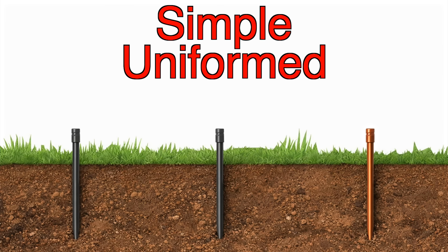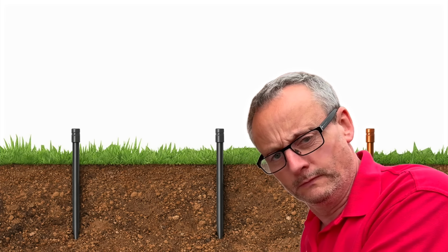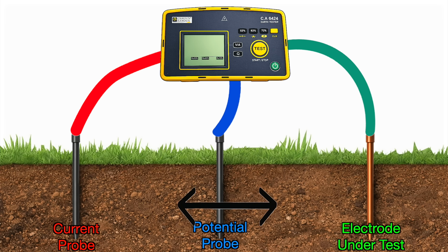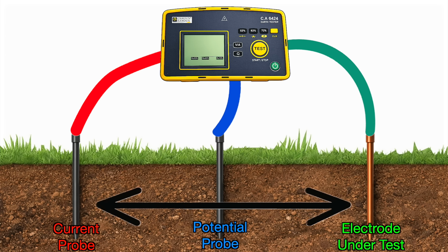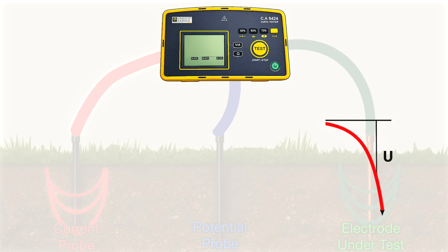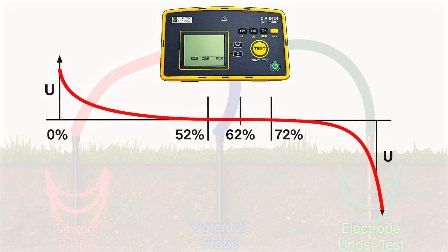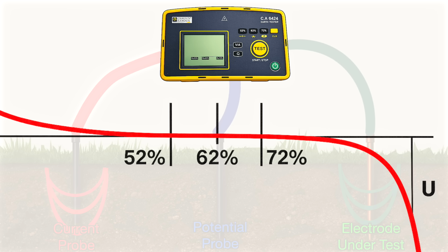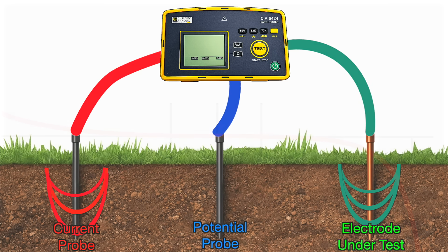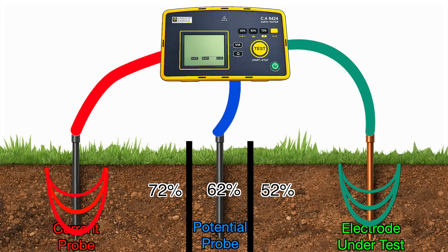In a simple uniform soil model, something interesting happens. If you plot resistance against distance between the electrode and the potential probe, the values rise and flatten out and then rise again. That flat section is where the influence of the current probe is minimal, and mathematically that flat point sits at around 62% of the distance between the earth electrode and the current probe, and that is why it's 62%. So now we're going to move on to earth fault loop impedance testing, or loop.